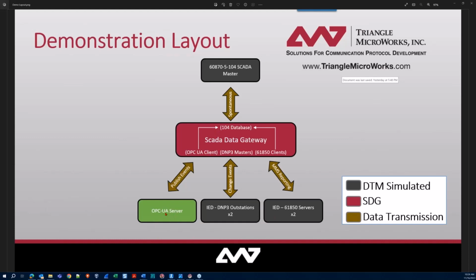So this will be an OPC UA server, and I'll have an OPC UA client within my gateway that's going to be receiving that data. I'll also have two DNP3 outstations sending data, and two DNP3 masters receiving that inside my gateway. Finally, I'll have two 61850 servers. These at the bottom will all be outside devices, and I'll be receiving that data inside my gateway, of course with a 61850 client. Finally, I'll be aggregating that data and providing it up to a remote SCADA master.